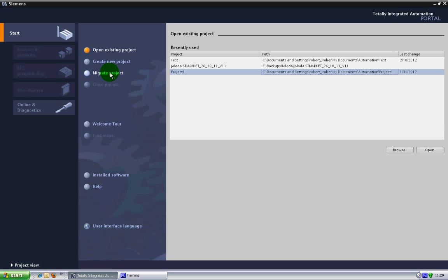I have seen a couple of migrated projects. However, you better be very, very careful with this because it doesn't do what you expect it to do. For some reason, when it migrates projects, it brings everything into OB blocks.